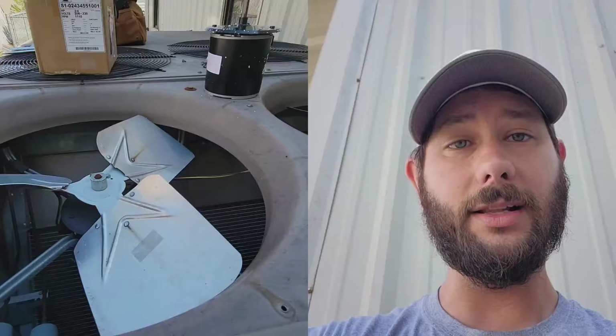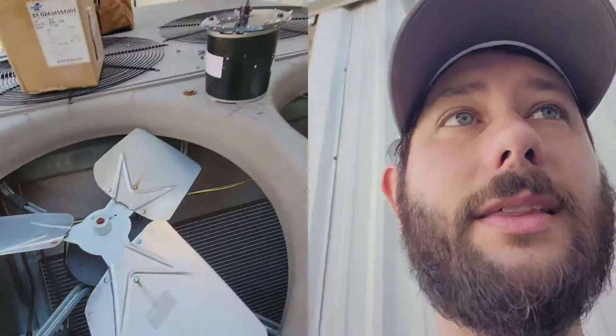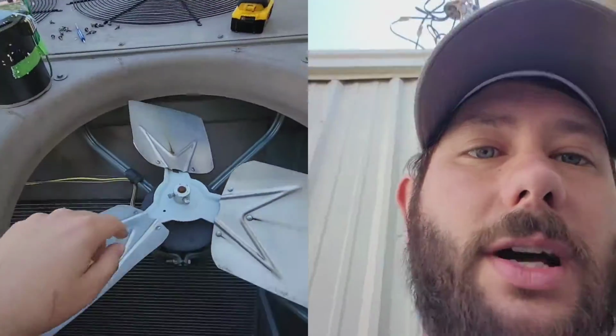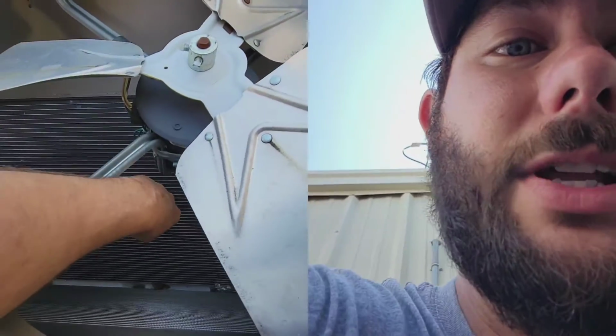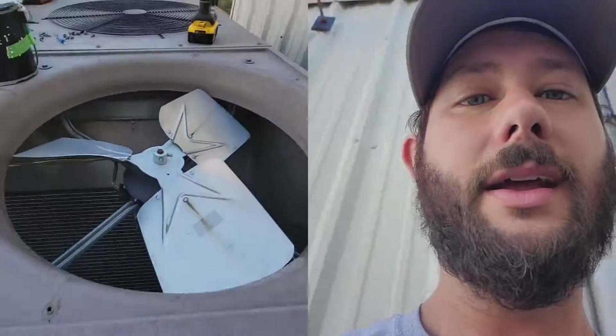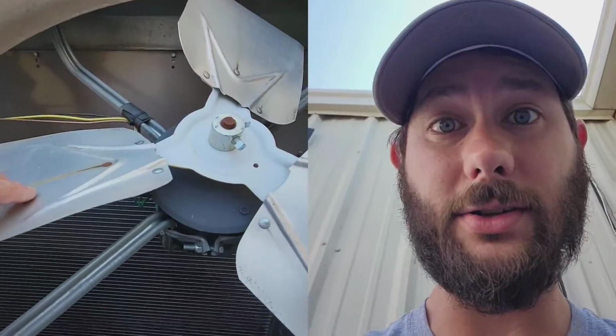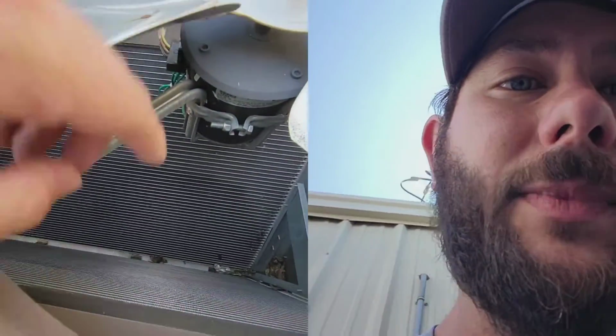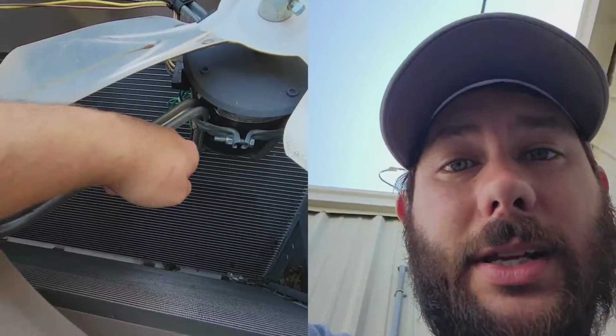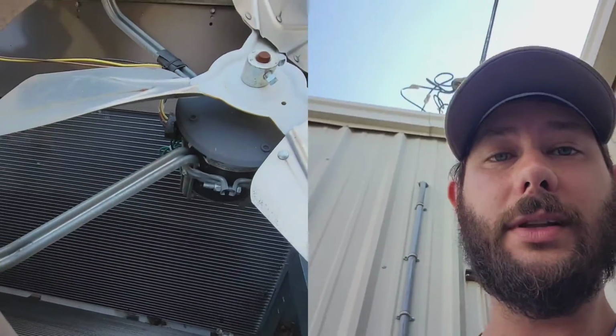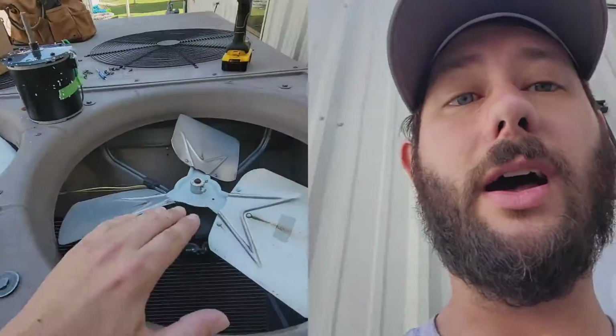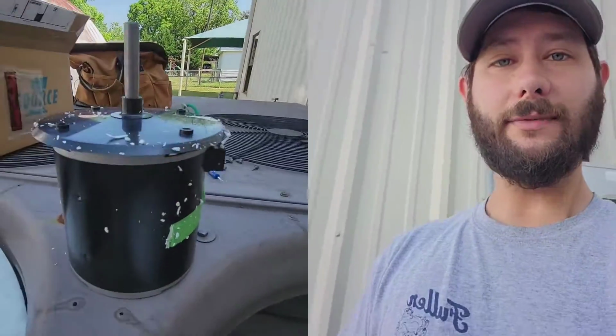Also, the way that I like to clean the coils is I like to take the little fan guards off here so I can reach down in here. Make sure you turn the power off at the disconnect and do a lockout tag out so you don't get your hand chopped off—you don't want that. So I get my water hose in here and I'm able to clean off that coil really nicely. I definitely like taking these off, and while they're off, I've got a motor here.